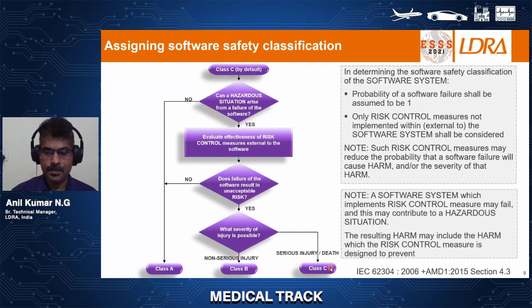The software safety classification has a tremendous impact on the software development lifecycle. So you can see over here, if it is a class A device, the manufacturer needs to comply with only a few subclauses as far as 62304 is concerned. Whereas if it is class C, you need to comply with all the subclauses, wherein all the activities and tasks need to be performed, completed, and accomplished as far as IEC 62304 is concerned.